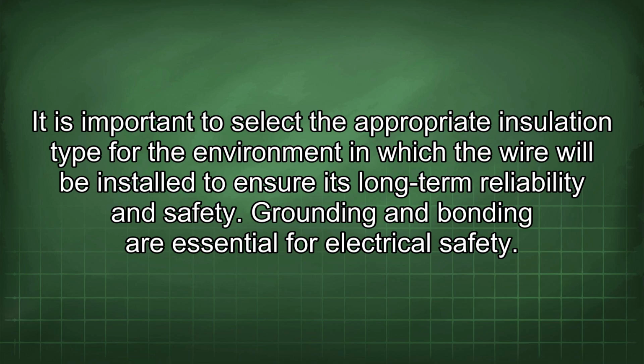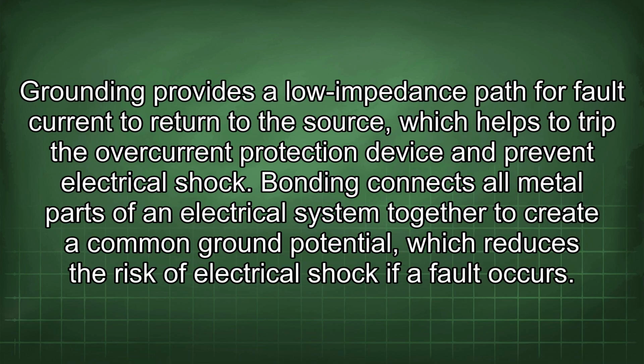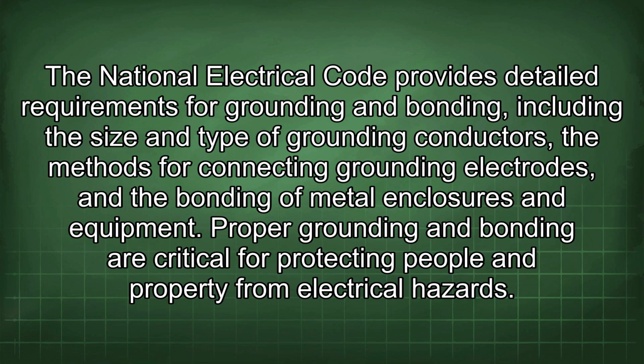Grounding and bonding are essential for electrical safety. Grounding provides a low impedance path for fault current to return to the source, which helps to trip the overcurrent protection device and prevent electrical shock. Bonding connects all metal parts of an electrical system together to create a common ground potential, which reduces the risk of electrical shock if a fault occurs. The National Electrical Code provides detailed requirements for grounding and bonding, including the size and type of grounding conductors, the methods for connecting grounding electrodes, and the bonding of metal enclosures and equipment. Proper grounding and bonding are critical for protecting people and property from electrical hazards.